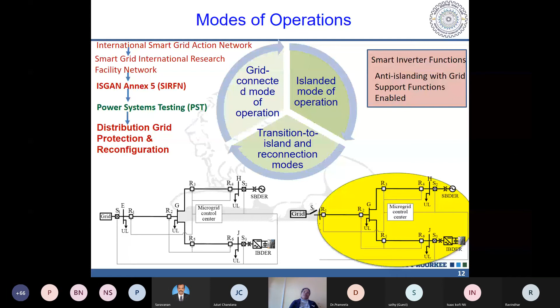And even then, if this unintentional islanding is not detected, so many issues are going to come. The first one is out of phase reclosing. Suppose this is a grid which is disconnected, and this is your microgrid. When this microgrid is disconnected from the main grid, what happens? The frequency of this particular microgrid changes. Why? Because when it is disconnected, the load and power generation don't match. It may also happen that loads and generation, basically due to the renewable sources, change. So this delta P, delta Q mismatch in active and reactive power may lead to variation in the voltage and frequency. So when we are going to reclose the switch again for the synchronizing process, this is known as the synchronization process.